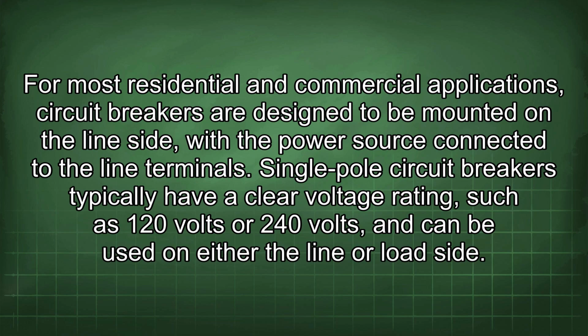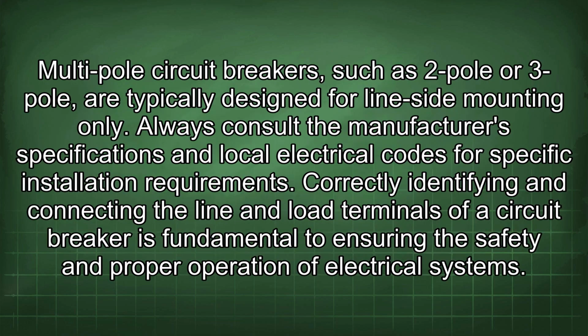For most residential and commercial applications, circuit breakers are designed to be mounted on the line side with the power source connected to the line terminals. Single-pole circuit breakers typically have a clear voltage rating such as 120 volts or 240 volts and can be used on either the line or load side. Multi-pole circuit breakers, such as 2-pole or 3-pole, are typically designed for line-side mounting only. Always consult the manufacturer's specifications and local electrical codes for specific installation requirements.